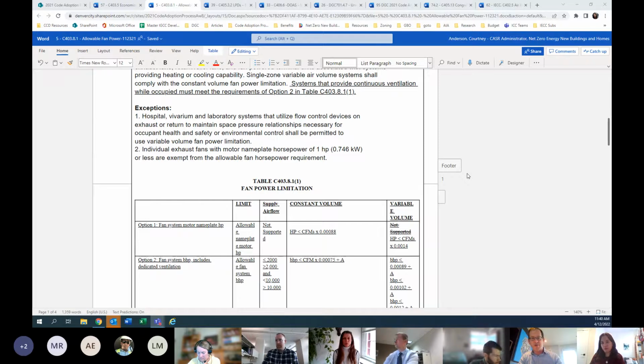And one thing to state in terms of resiliency, at least with the kinds of rooftop units and package units and systems that I see in the field, those typically have a lifespan of 15 to 20 years, whereas the ductwork often stays in the building for quite a long time. So we want to make sure that it's being designed in a manner to minimize the static pressure as much as possible, such that the fan systems can be reduced in size where possible.